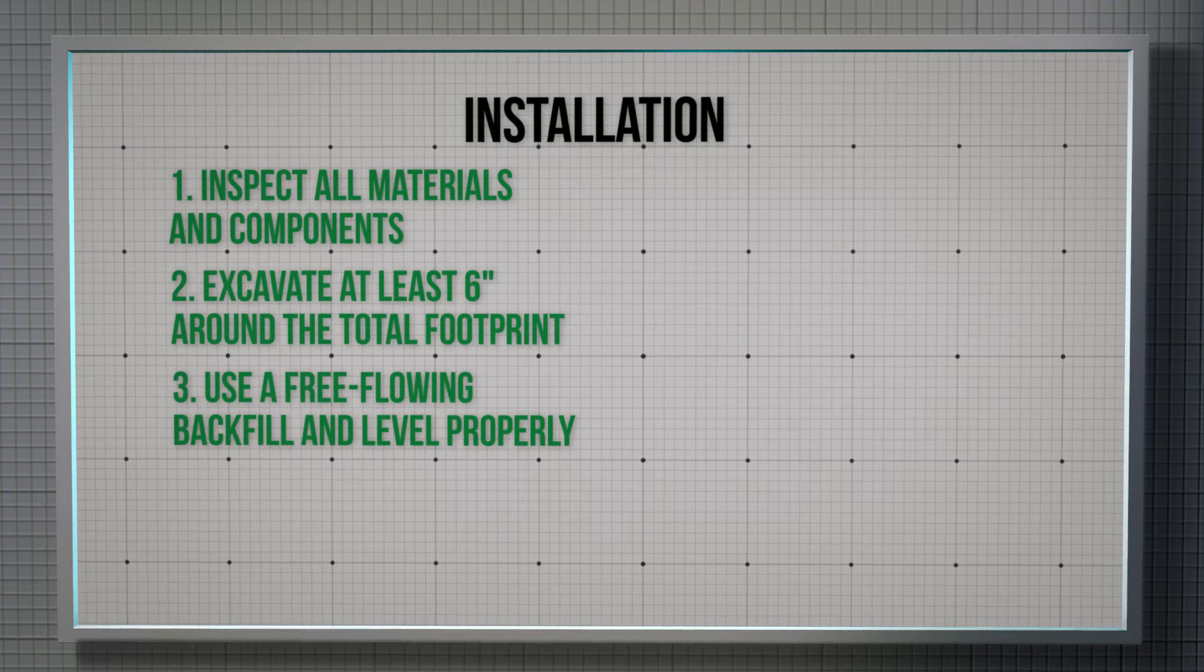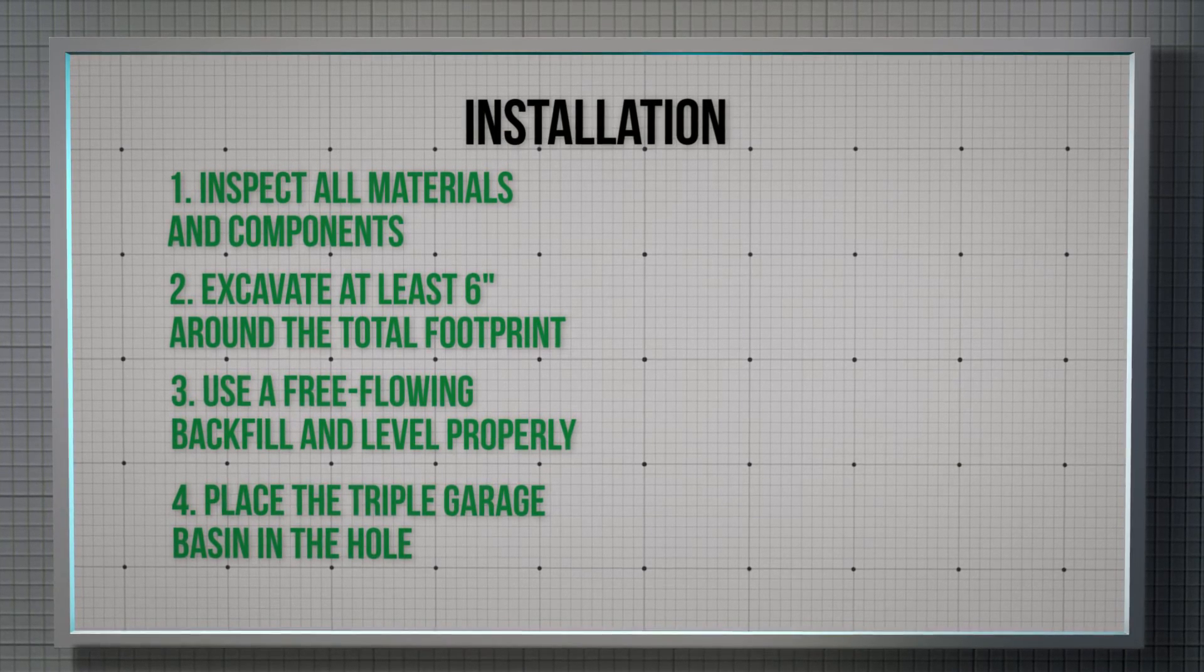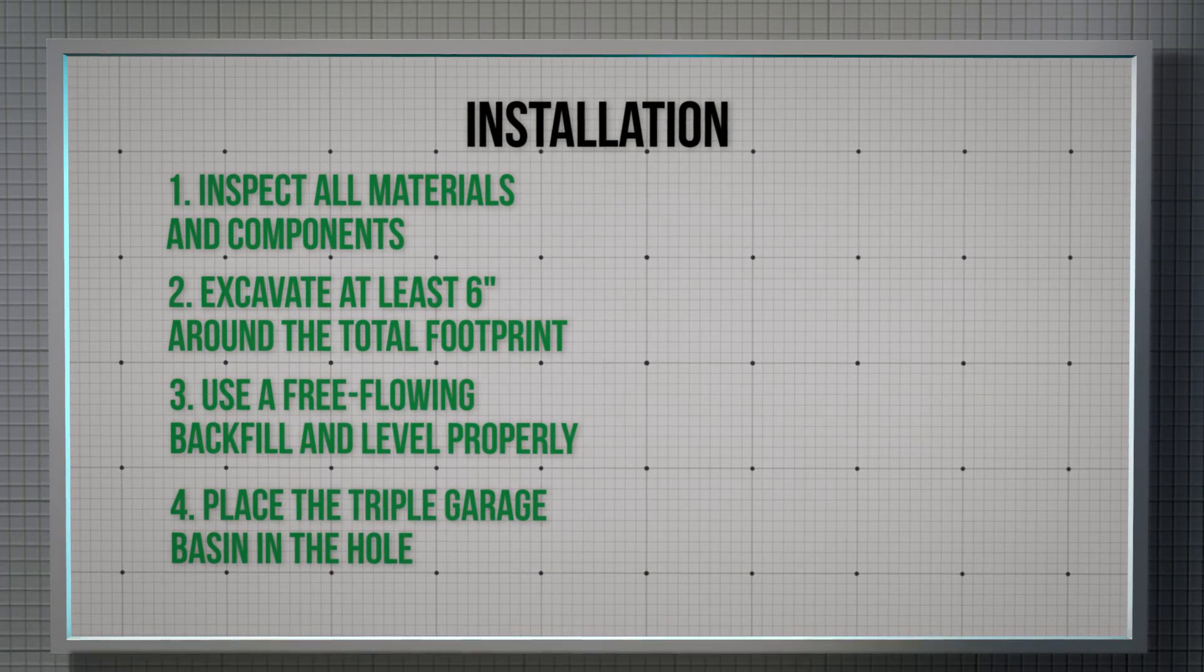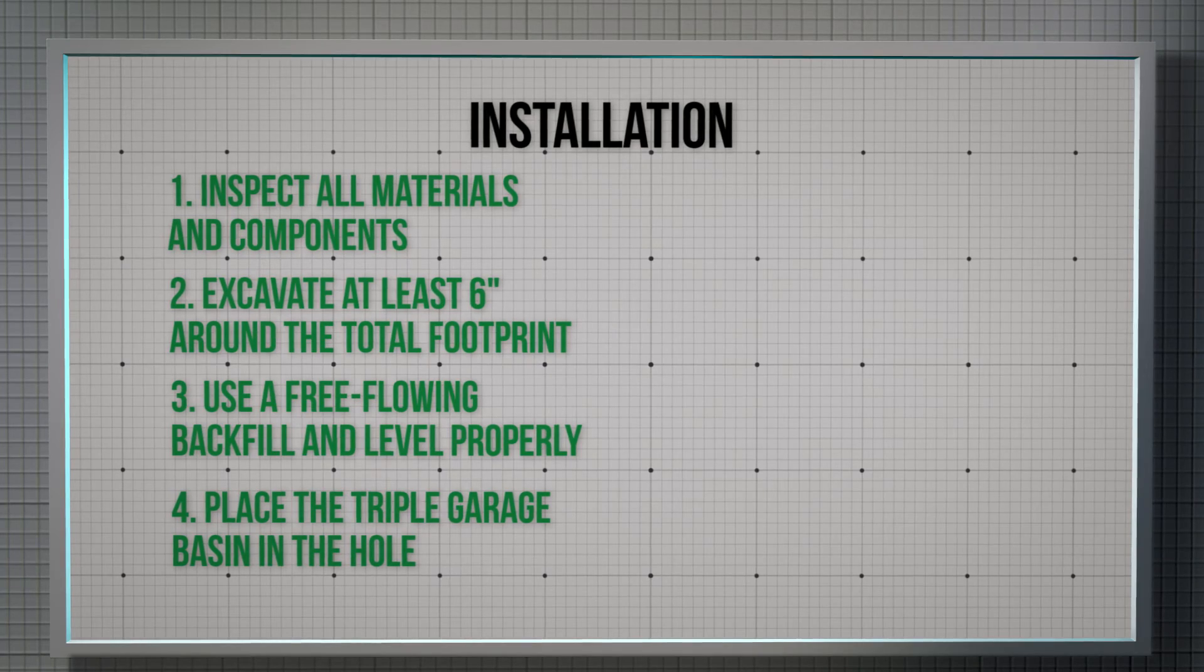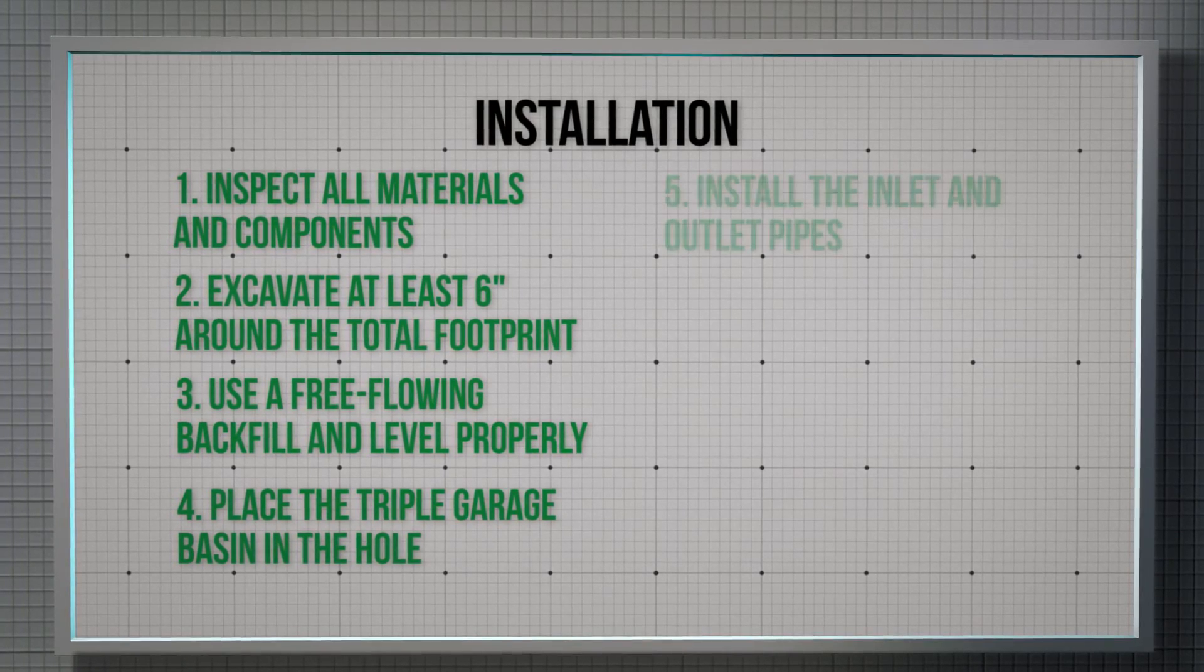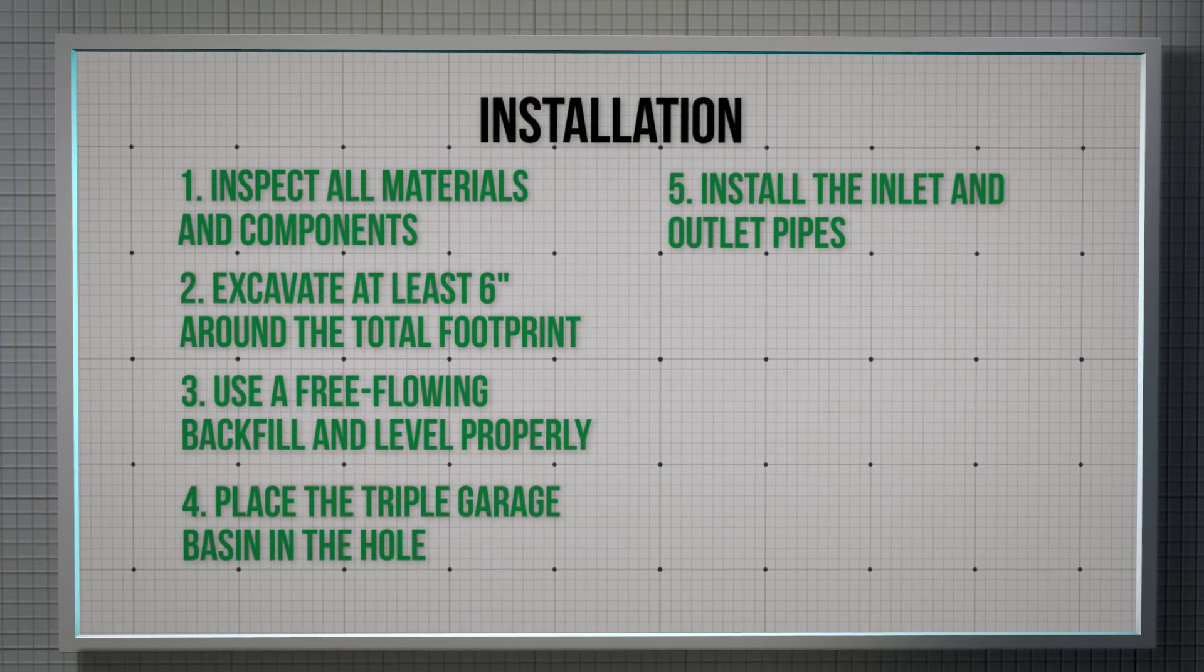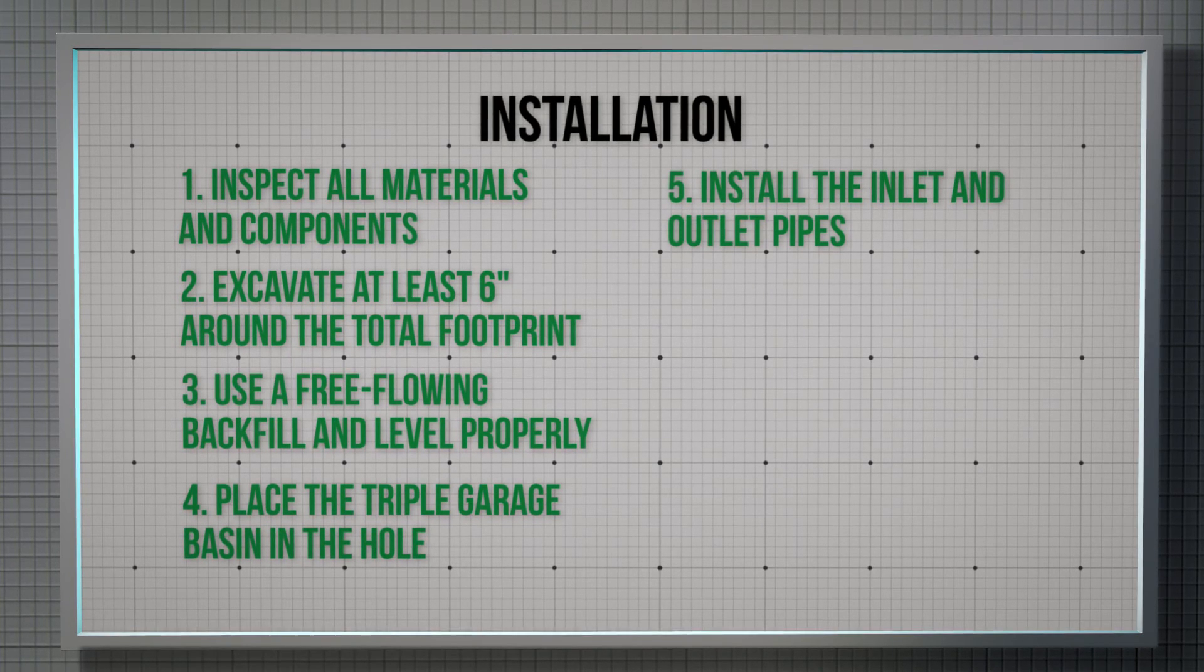Place the Triple Garage basin in the hole according to the vent direction so that the basin can vent properly. Double check to make sure the Triple Garage system is level. Install the inlet and outlet pipes to the cast iron hubs to connect the Triple Garage system to the wastewater plumbing.